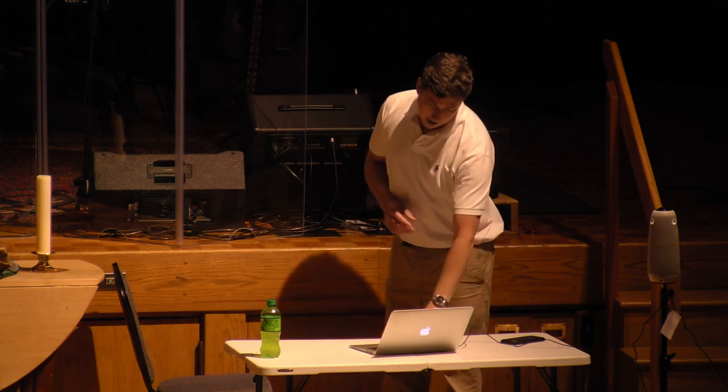Okay. So the minimum SEER, if you're looking at one of these devices, is 14. Next year, that goes up to 15. Good. That's better. If you have a system that is older, it could be 13. If you have a system that's somehow still living from the 90s, it could be a SEER 10, and it's probably lost some efficiency again, so it's probably very inefficient. So making any kind of upgrade, even to a SEER 15, which will be the minimum standard next year, will pay big dividends.